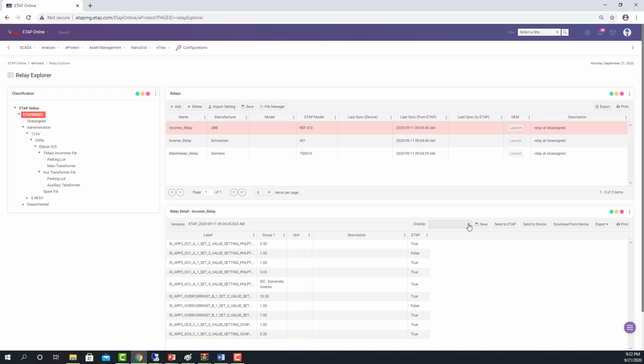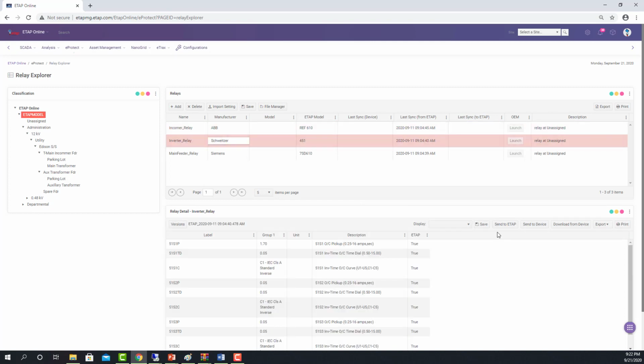So, for example, if I wanted to change any of the settings here, if I have again the right permissions, I'm going to first save the current. Let me go into this relay here. It looks like I don't have the right permissions. Sorry about that, but I would be able to come in here, save the current configuration. Then it will allow me to make a change to the settings, and then send the settings to the device. So that means that from one central console within the substation, I will be able to make the setting changes from here. I can also download from the device.